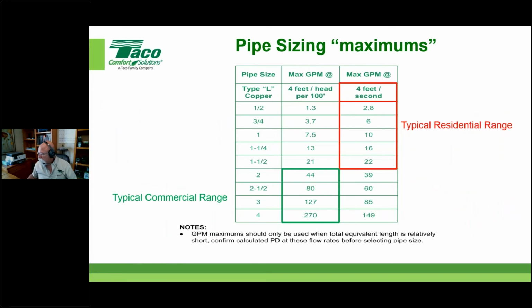Can they be the same size? They can be the same size, especially if you go back to where we were talking about piping in series, right? That way the total flow of the system is going through the boiler. With that in mind, you would want the same pipe size.